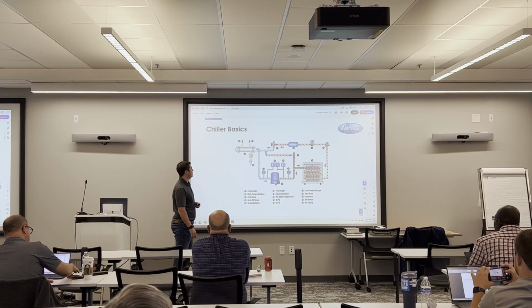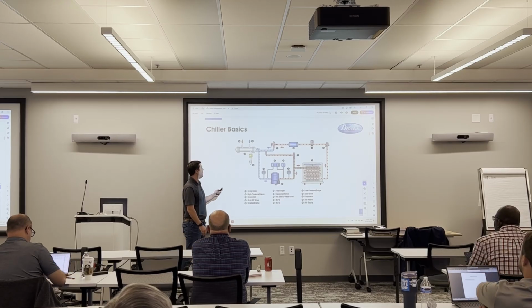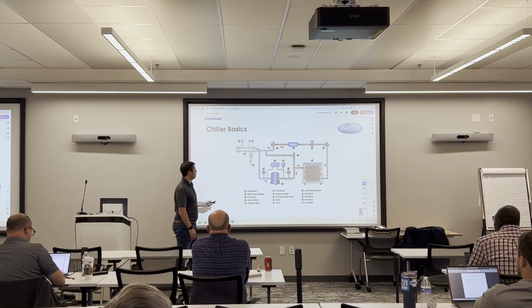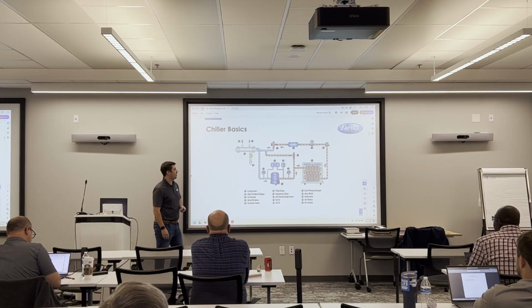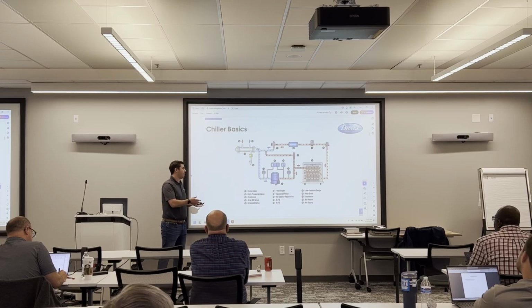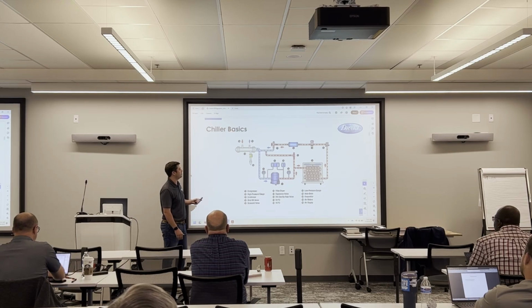It's important that it boils off into a full gas because as it travels out of the evaporator and into our compressor, these compressors cannot compress liquid refrigerant. So we've got to ensure we have superheat coming out of our evaporator. Otherwise, it's going to be bye-bye compressor. Your compressor, we're not very creative with the names. In our industry, the compressor takes that low-pressure gas and compresses it. It's the driving force that allows the refrigerant to flow through this whole circuit.